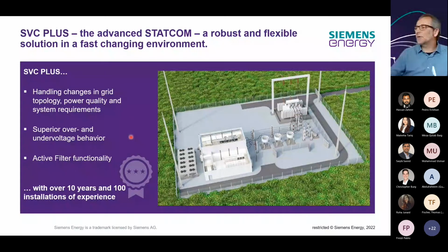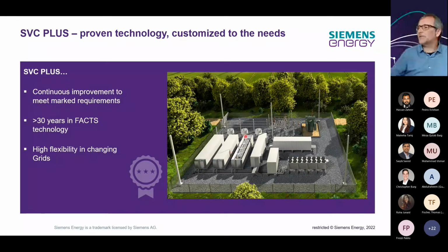There are different configurations available. We call it open rack, so it's in a building: there is the converter and the control room. We also have a containerized version. We use single phase containers for bigger applications and a 3-phase container for smaller applications. It depends on the requirements. Normally, our customers will tell us the size of the STATCOM, and it is for us to decide which would be the most suitable one: open rack or containerized, single phase or 3-phase containers.